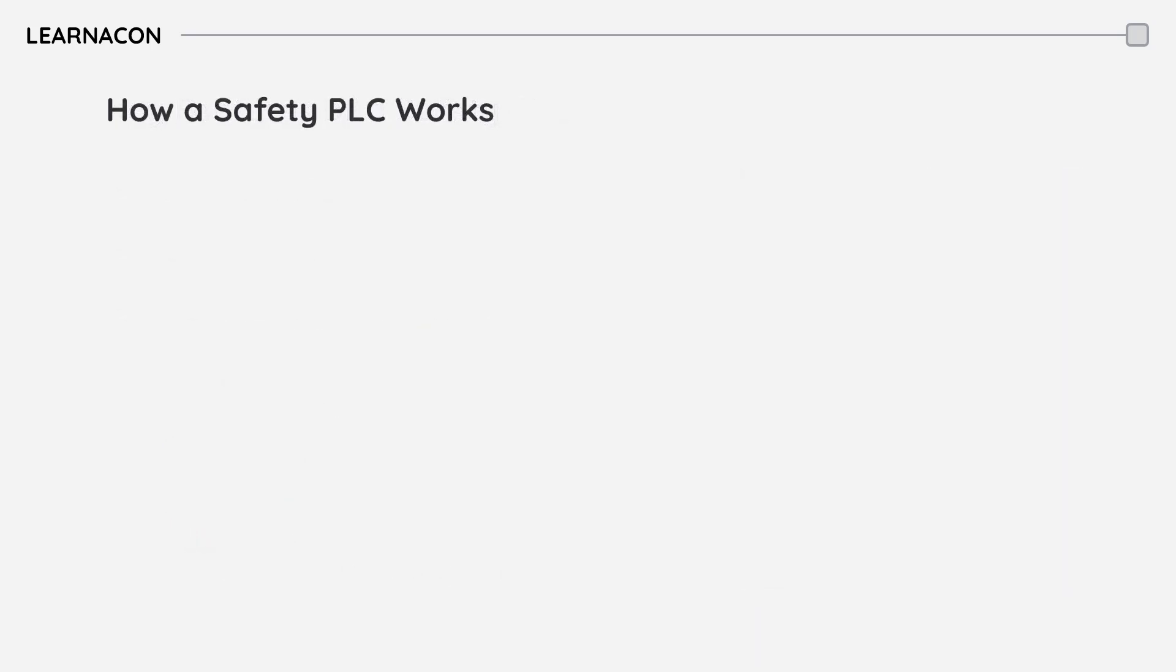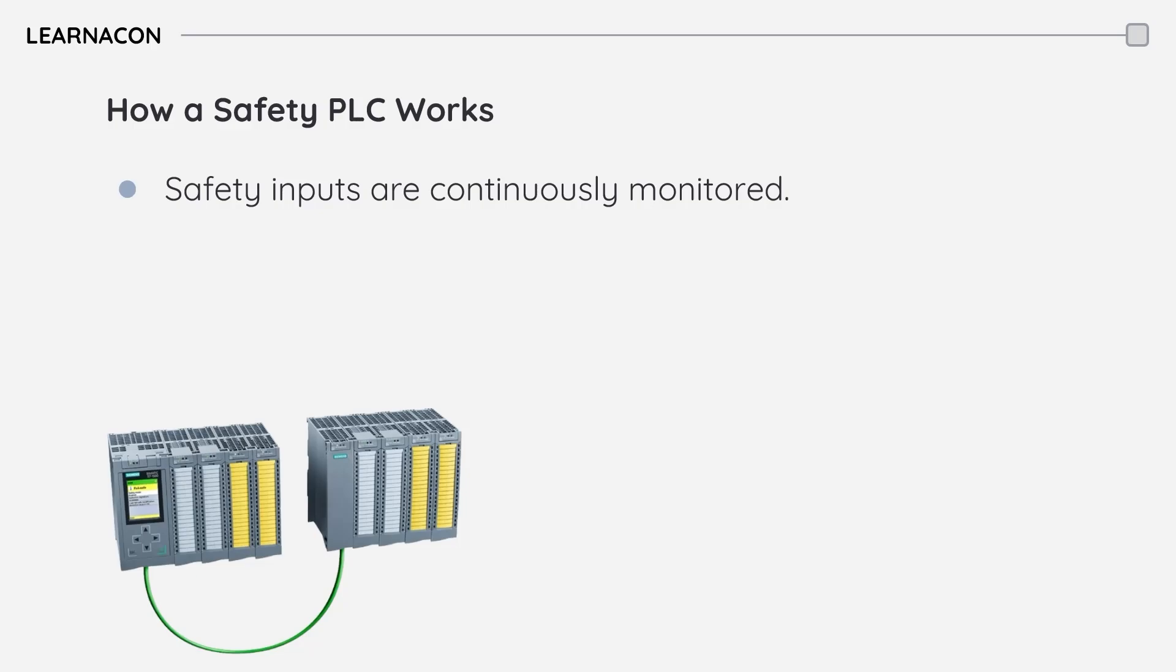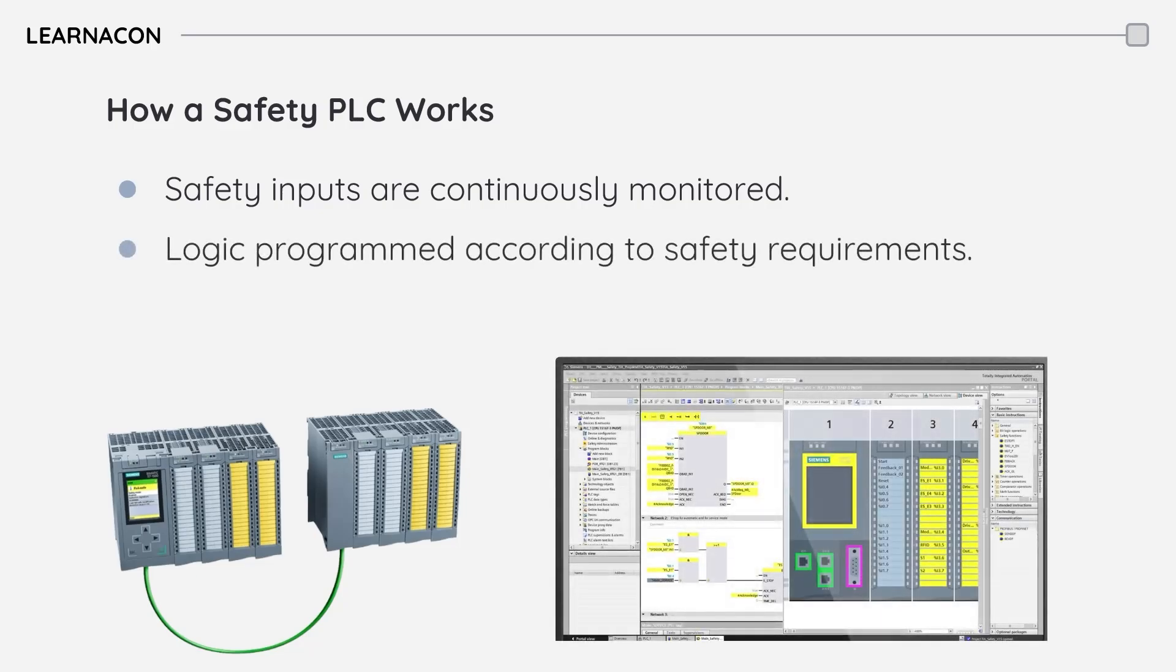Let's take a look at how a safety PLC works. It all starts with continuous monitoring of safety inputs. These inputs might come from emergency stop buttons, light curtains that detect if someone has entered a restricted area, or other safety sensors. The safety PLC then executes the safety logic that has been programmed according to specific safety requirements.